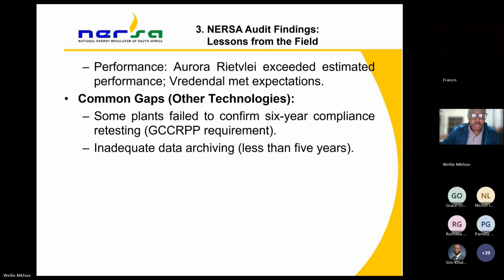As I said earlier, some of the plants do fail to confirm the 6-year compliance retesting, and we've seen quite a number of applications for exemption in this regard, for various reasons, ranging from software upgrades to equipment not meeting certain testing criteria. It's important that plants are properly maintained throughout the 6-year cycles, so that when it comes to the testing after 6 years, they are able to meet those requirements as outlined in the grid code. We could talk more about the specifics of what the tests are, but I don't think we have enough time here.